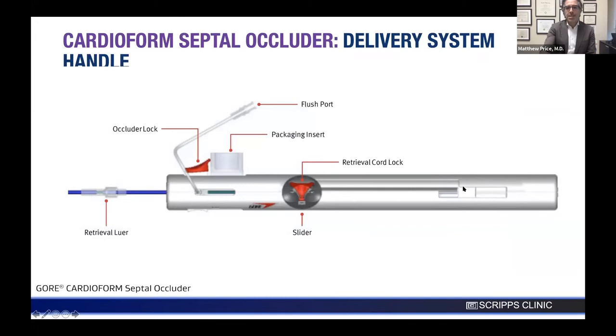So first, there's a slider, and there's this Z track, they call it. Well, it's more of a U if you ask me, but it'll come out like this when it's coming out of the package, where the occluder will be outside the delivery sheath. So you'll need to load the device, and all you do to load the device is slide the slider away from you along this track, and then down and then back. And that's going to bring in the right disc, then the left disc entirely. There's a flush port. So what we do is we load the device and then flush the system. You'll need a stopcock there to do that.